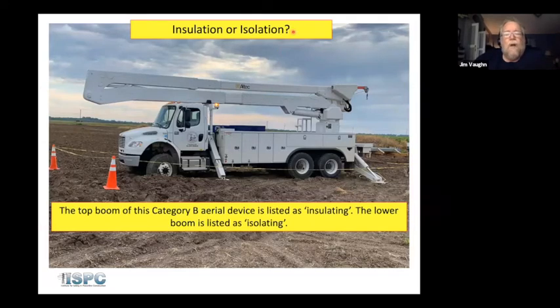Now, on this category B device, this also makes a difference on our MAD and how we cover and what we do. And I've got a lot of linemen who make the mistake of thinking that this boom is what creates your isolation. Now, it's true that we test this boom, but this boom is not considered your isolation. Your primary means of isolation are your rubber gloves and the hot sticks that you use. In a category A bucket, this boom is your isolation, and it creates the isolation of your bucket in the air so that you can make energized contact with that circuit.